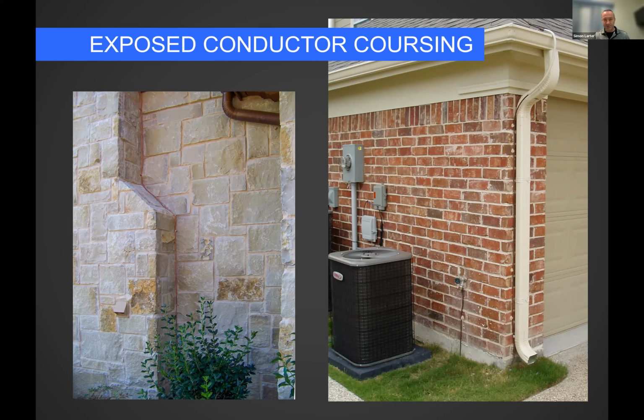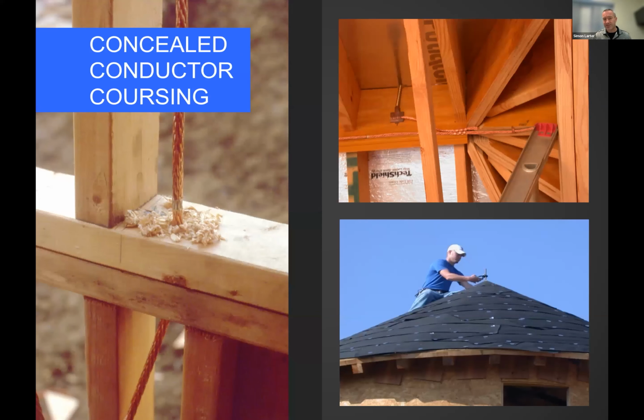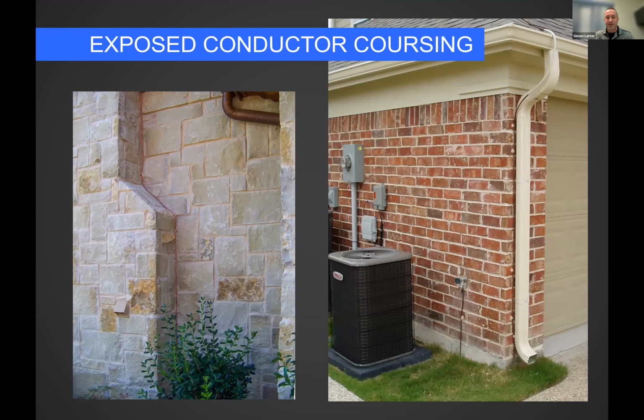But when we certify a building through the Lightning Protection Institute, or Underwriters Laboratories can do it also, but we do third-party certification a lot through the Lightning Protection Institute primarily, we have to take pictures of all our concealed conductors and our grounding, and we submit those. We submit an as-built drawing to their engineer. They review everything. Sometimes they will send an inspector out to do an on-site physical review, but we have to keep records. If we conceal it behind building finishes, we should know what it is. We should as-built it, redline it, and make sure we have photographic records to ensure that it was done properly. Even though the conductor is concealed behind building finishes and the building looks beautiful now, we still know we did it correctly and we have a record of that.